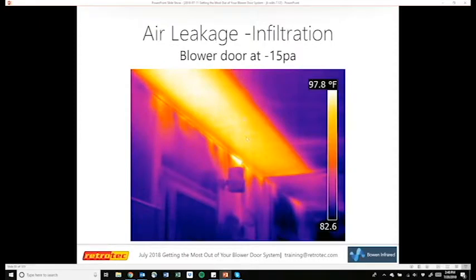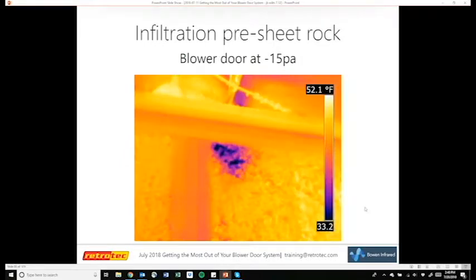Here we have a combination of a number of problems. Here we have the blower door at -15. This is the one where we turned it up a little bit just to get the airflow down into these walls. So this area of this particular home is missing a large amount of insulation in the ceiling. It's quite evident in the image here. But what's also showing up is, and again, Sam emphasized in some of the pictures that he had, where the top plate is not sealed correctly, and then we've got attic air flowing down into the interior walls, and we can see that patterning quite emphasized with the air being pressurized or negative pressure at -15. Very indicative of interstitial airflow.